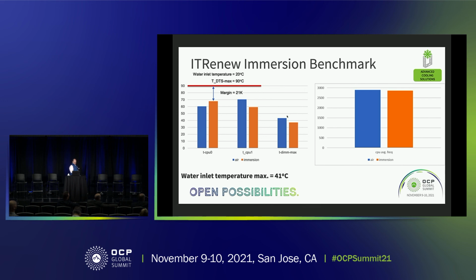The references are the CPU 0 and 1 position switches because the server is inverted in immersion. But the main point here is that we have 41-degree warm water inlet temperature performance achieved. Slightly lower, or actually 10 degrees plus lower than that predicted from the simulation, but there were some compromises on the build regarding heat sinks, which we're working on together with ITrenew.